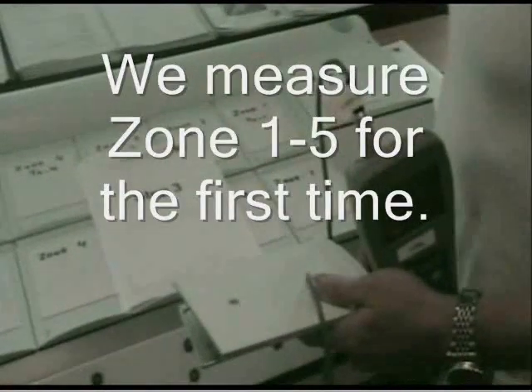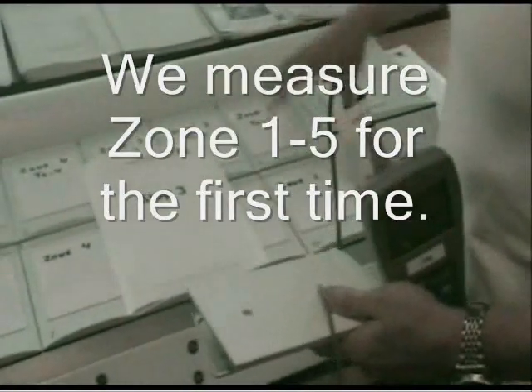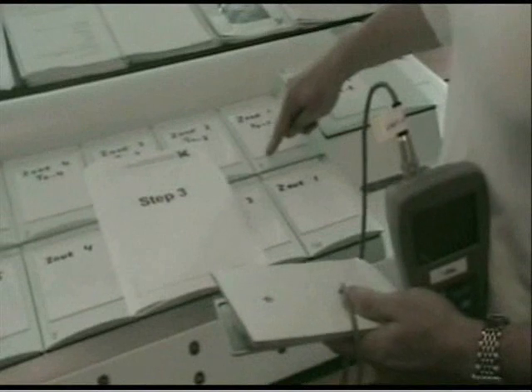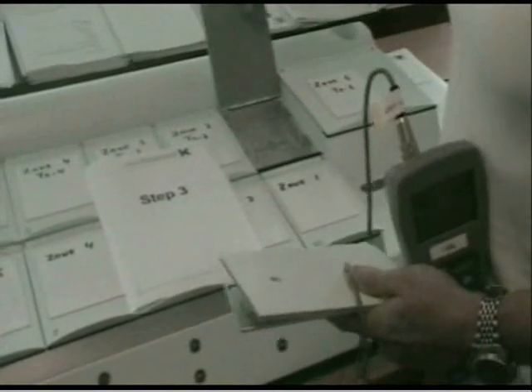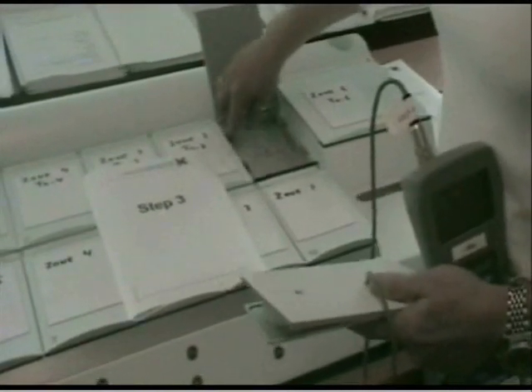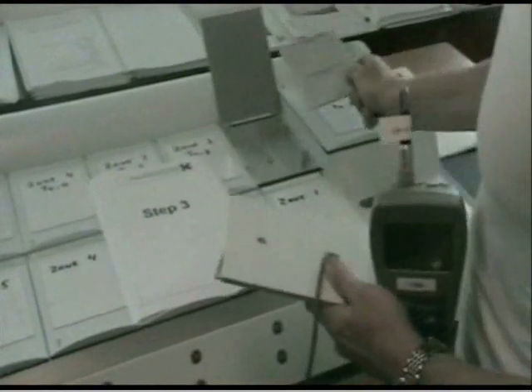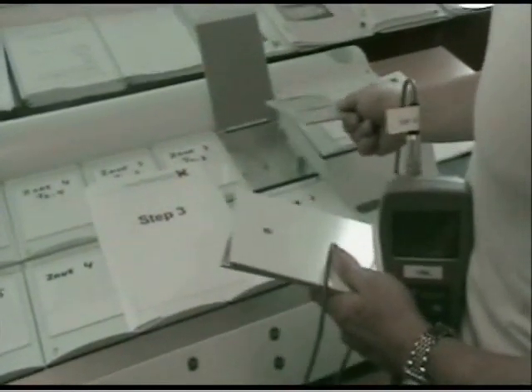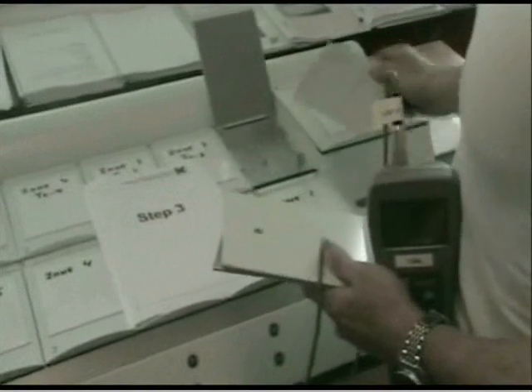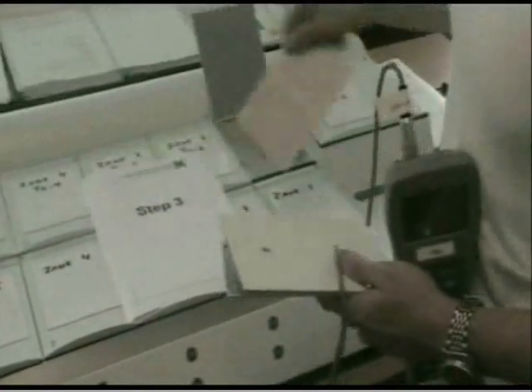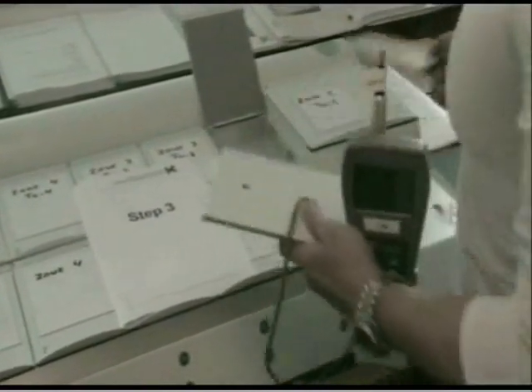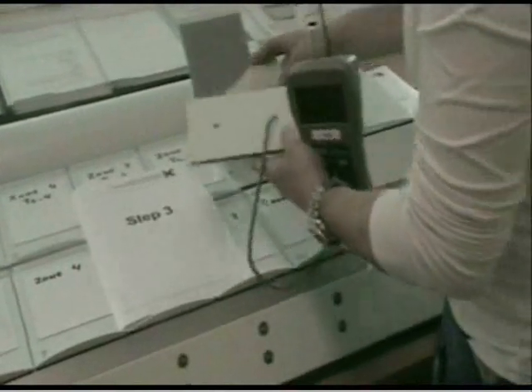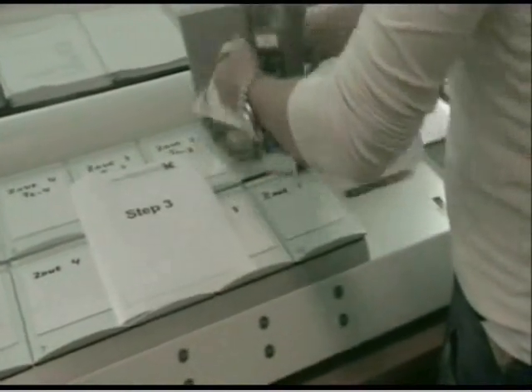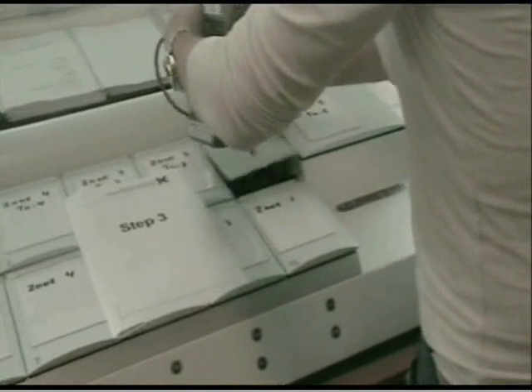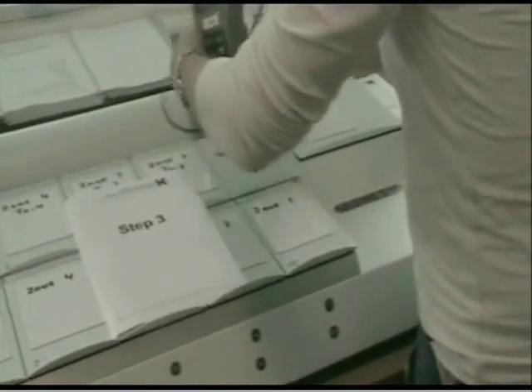So now we start doing the actual measurements. We start here in zone 1 in compartment 5, and we take out the warming plate inside it. Put this aside, as we're not going to use this anymore during the calibration. Make sure that you have the heating inserts in all the compartments. This is very, very important. So now we put the temperature sensor inside. Make sure with the test lid that it's sealing well.